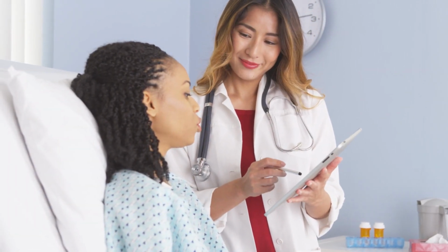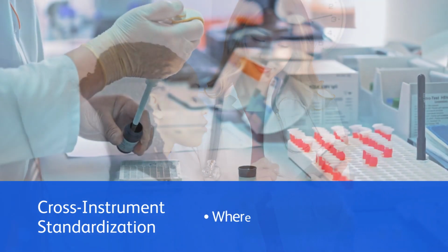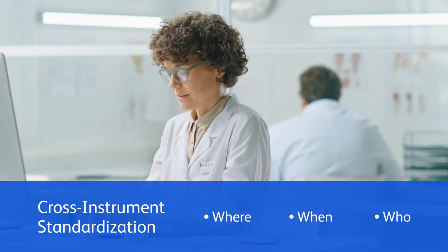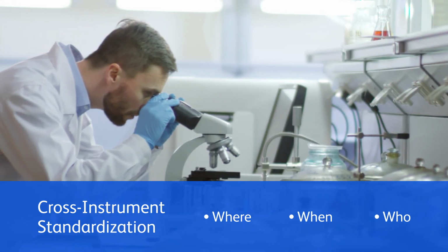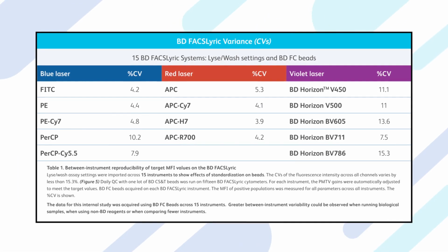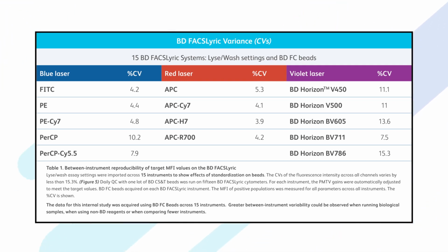The primary objective of cross-instrument standardization should be to issue the same patient diagnosis or to produce the same experimental result, regardless of where, when, or who analyzed the samples. The complexity of multi-instrument standardization varies depending on the number of labs, instrument platforms, and intended use. Use of CS&T beads to automatically adjust PMTV gains to meet target MFI values allows cross-instrument and cross-site standardization on BD FACSLyric.